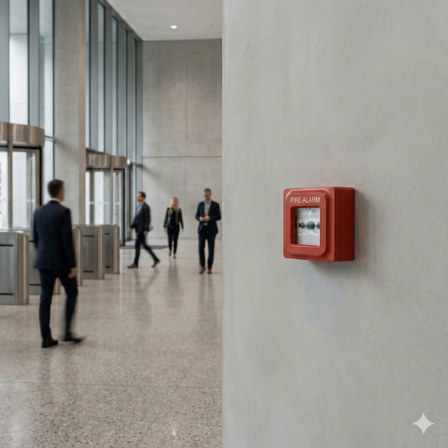And finally, the most crucial interface of all: the fire brigade interface. What do responders need to see when they arrive? Local codes mandate standardized interfaces and displays, usually in a fire command center near the main entrance. These displays have to show the full current system status, the exact address of the device and alarm, the status of power supplies, any trouble signals. This data access is mandatory, and it's what their initial tactical decisions depend on.